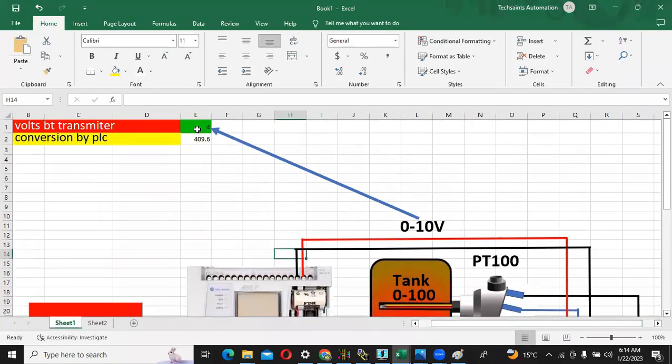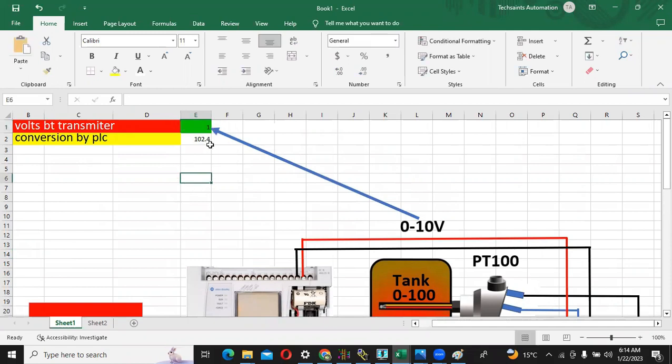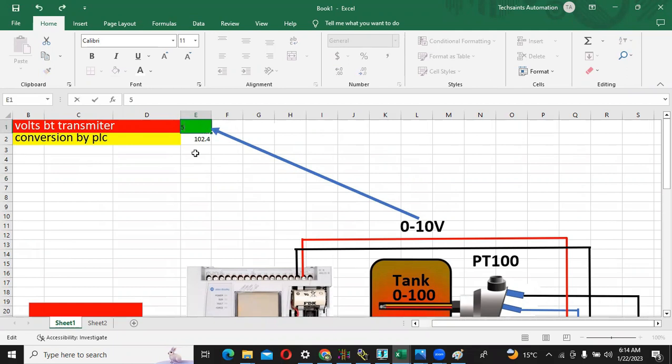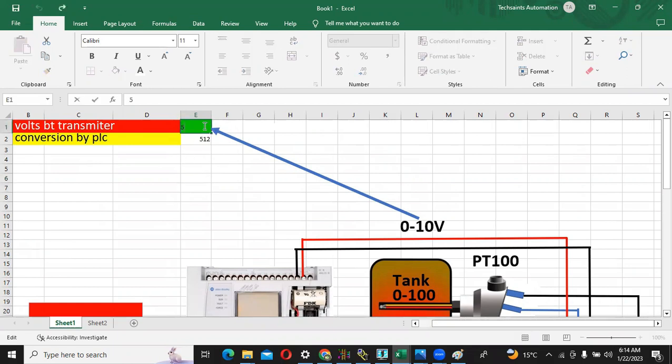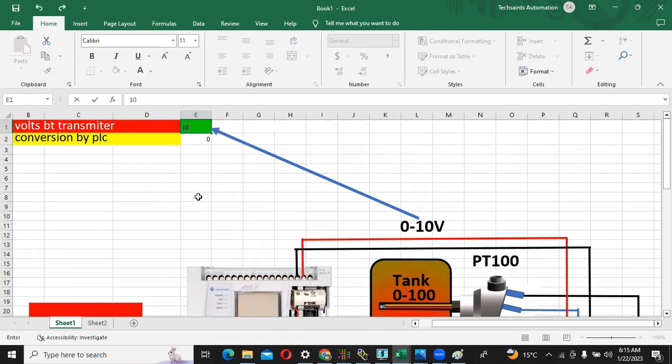If the PLC is receiving 1 volt, the value will be 102. If receiving 5 volts, the value will be 512. If this transmitter is giving this voltage, PLC gives this value to the processor. The converter will give this value. If the value is coming here 10, the value will be 1023.